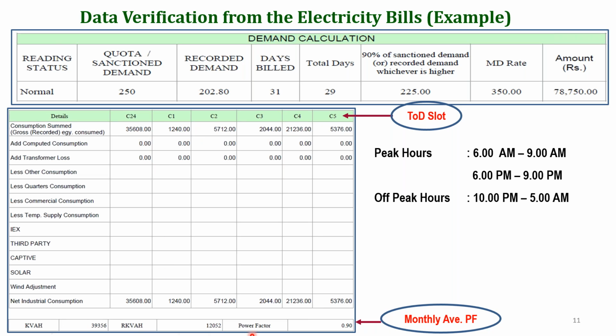Now this is the maximum value reached for kVAh and similarly RkVAh, and this is the average power factor of the industry for the particular month. This is the value they have for the month. I want to tell you that in Tamil Nadu, for HT industries, the minimum power factor is 0.9. For LT industries, the minimum value is 0.85. If it goes below 0.9 or 0.85, a penalty will be imposed. If it goes above 0.9 and 0.85 for HT and LT industries respectively, they do not offer any incentives, but the penalty will always be there.